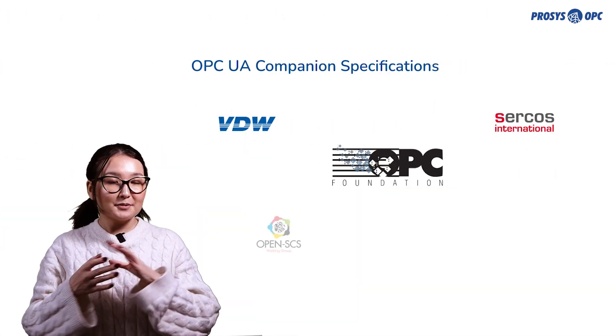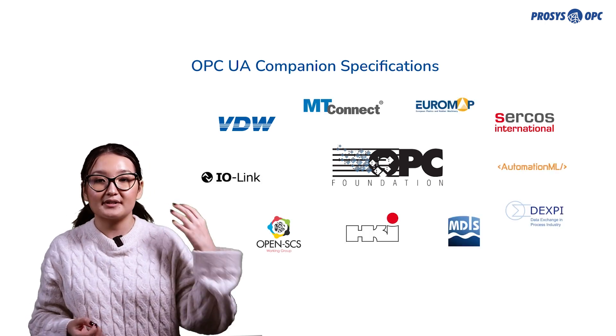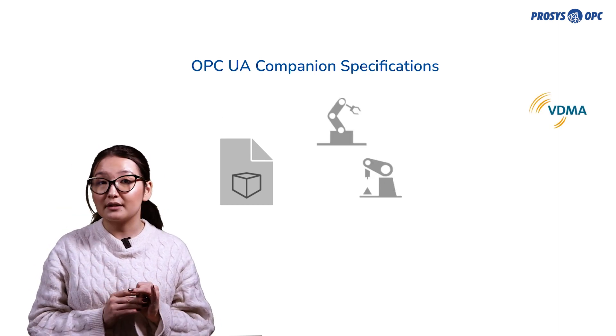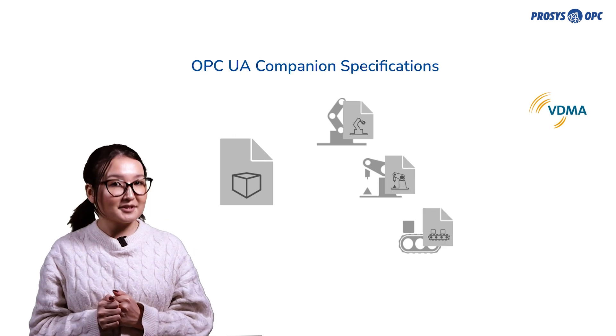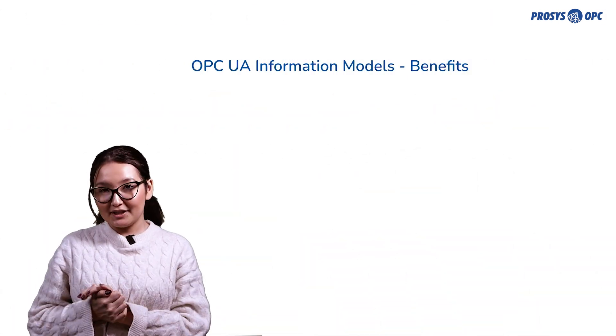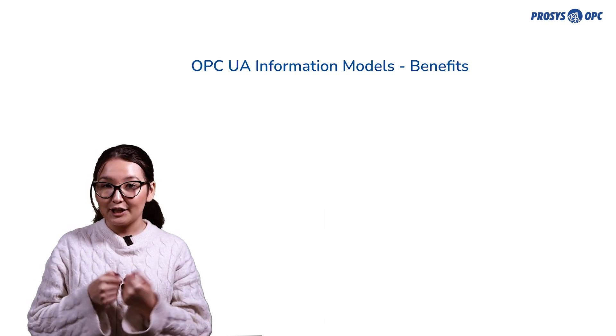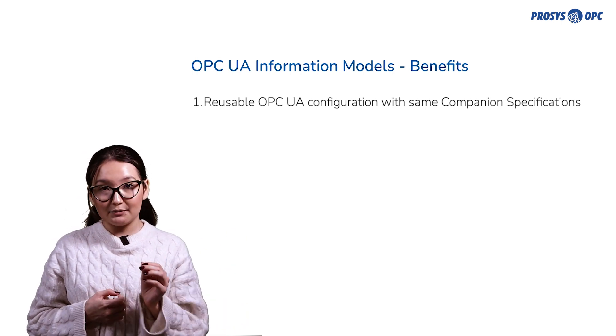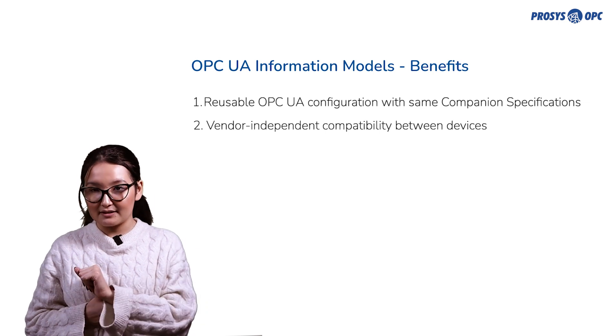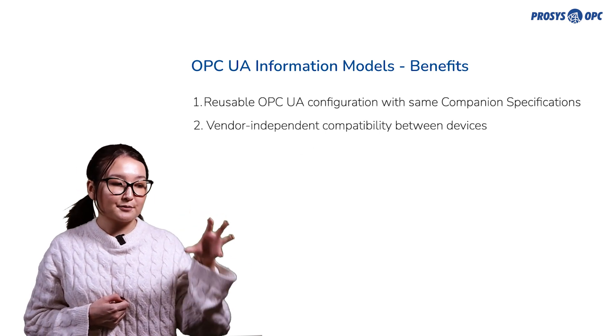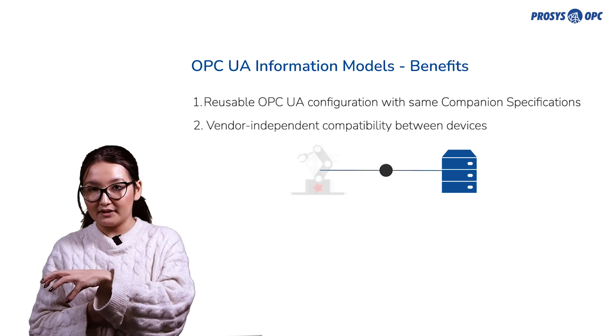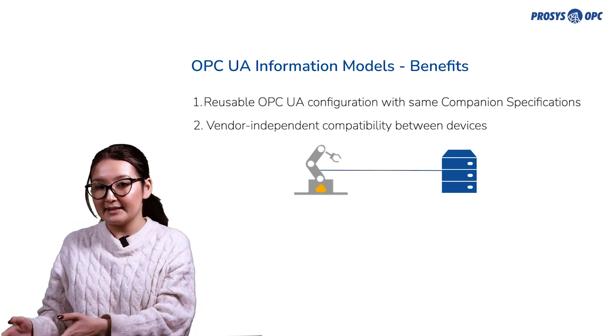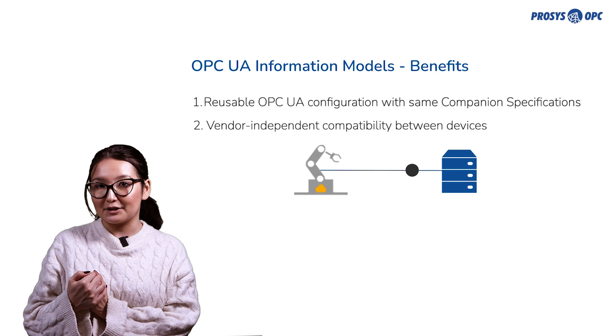Since the beginning, OPC Foundation has worked with different organizations to produce and standardize information models for various industrial domains, such as robotics, machine vision, and plug-and-produce machines. And this is what we call companion specifications. The benefit is that you can use the same OPC UA configuration for every machine with the same companion specification. The second benefit is vendor-independent compatibility between devices, meaning you can replace a device from one vendor with a device from another vendor without disrupting any OPC UA connection, because the corresponding values are located in the exact same place in the information model hierarchy. And this is what we call plug-and-produce.